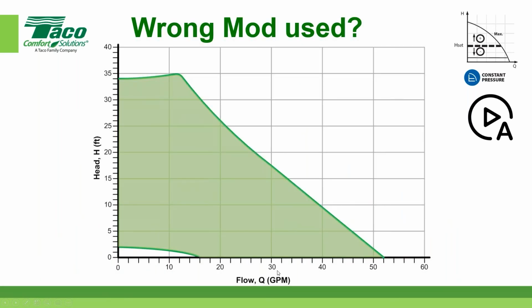Now let's map that out. 35 gallons a minute, that's 30, and there's 40, so somewhere in between there, right? 35, and there's my head, and there's my operating point under a design load condition with everything calling. So make sure you get that. Okay, that's the worst case. And if we're doing our load calculations correctly, we're doing our design correctly, appropriately, and we're not going to throw a bunch of fudge at it, right? The only time we're going to need this operating point, ASHRAE tells us about 2.5% of the season. So at 97.5% of the time, this pump is oversized. That's why we want to use it to its greatest ability for turning itself down and slowing down and giving us better overall system efficiency.